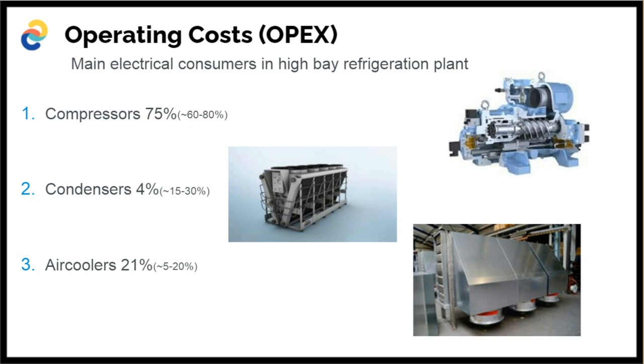For one cooler like this, you have a couple of fans. They are 7.5 kilowatts each, so on average you are looking at between 150 kilowatts and 200 kilowatts of electrical power for all the coolers in a high bay. So that's quite significant if you look at it on a yearly basis.